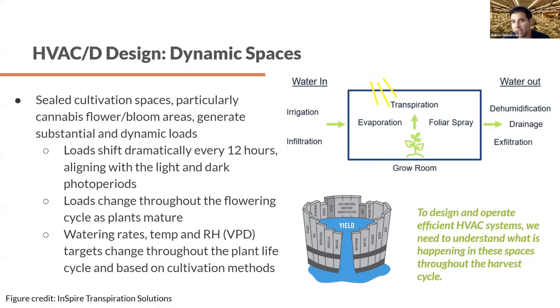It's a very dynamic load that completely flips. And yes, there are analogies to an indoor pool facility and natatorium types, but I don't know what the metaphor would be, but that pool doesn't stop emitting moisture half of the day, or reduce it down by 50 to 75% for half of the day, and have that cycle flip every single day. So we're going from a very high daytime period, the lights on period, where we need to remove a lot of moisture, and then the lights shut off. There's no heat load anymore, just like that. And we still need to remove moisture, just not quite as much. And so really understanding your watering rates is one of the most important keys to sizing these facilities and these systems appropriately.